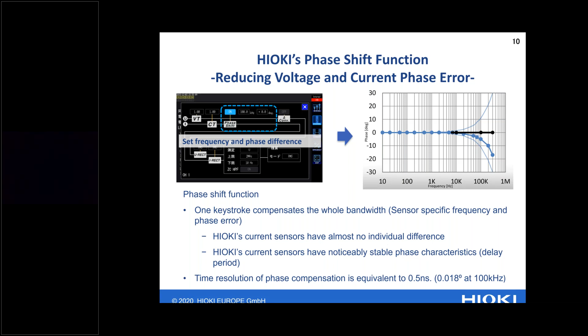In order to compensate that, and our analyzers are aware of the characteristics of each sensor, we have the function of phase shift correction, which can be switched on but also kept off in the power analyzer. So when you look at the chart, around 10 kilohertz we have a start of a shift, and you want to get that shift corrected. So at the end of the day, what's happening is we know the deviation, and our power analyzer will add that automatically to the measured result, and this will then lead to a more accurate result because of the addition of the miscalculation.